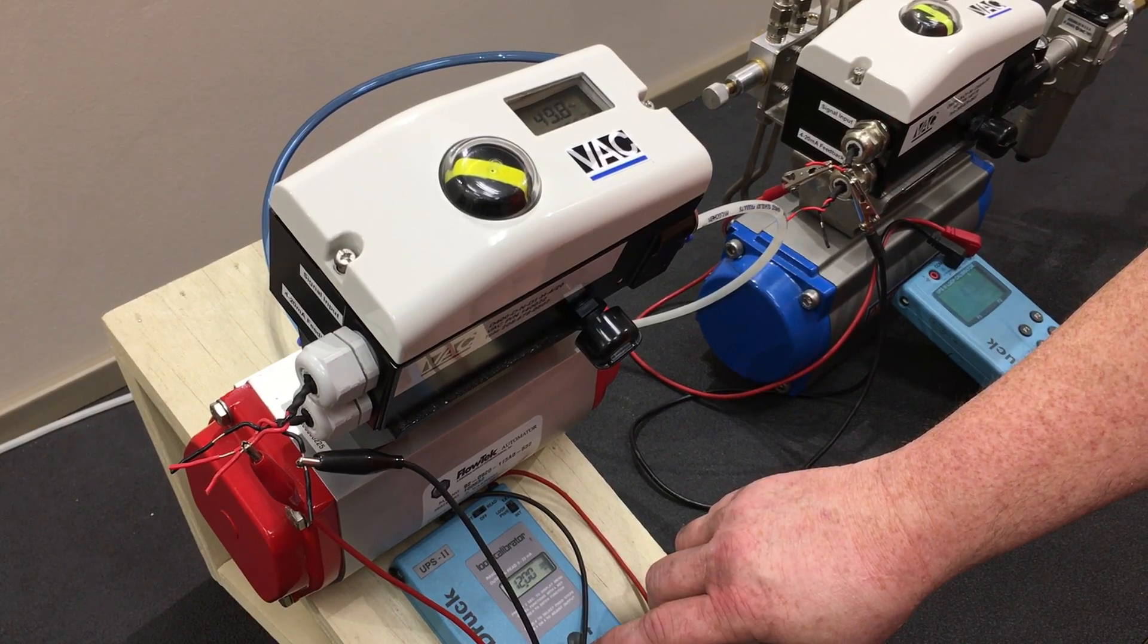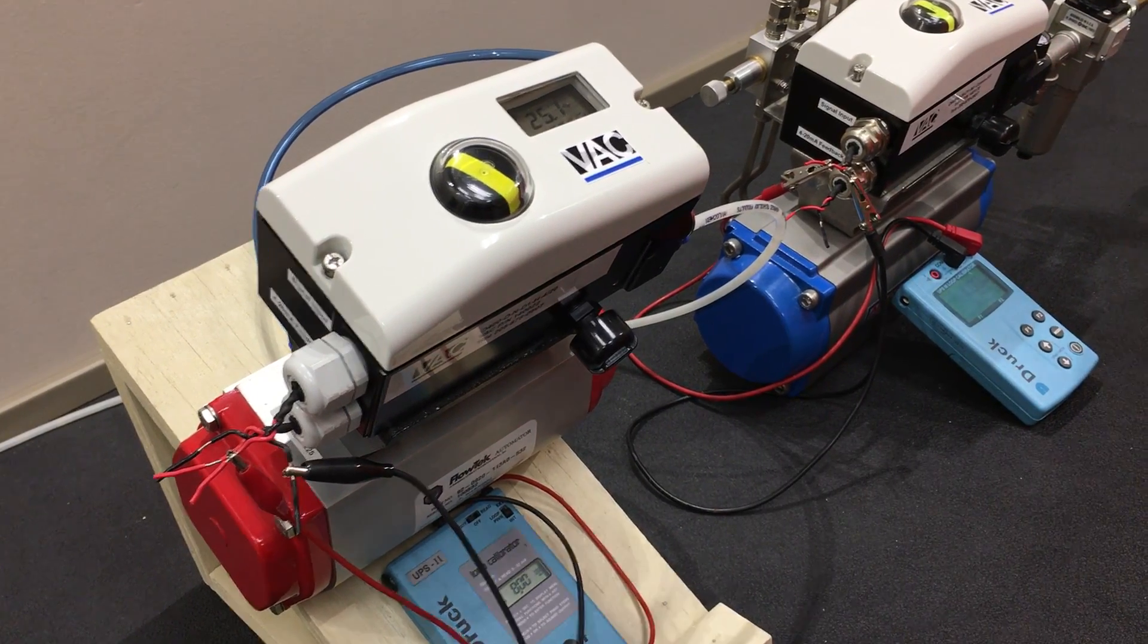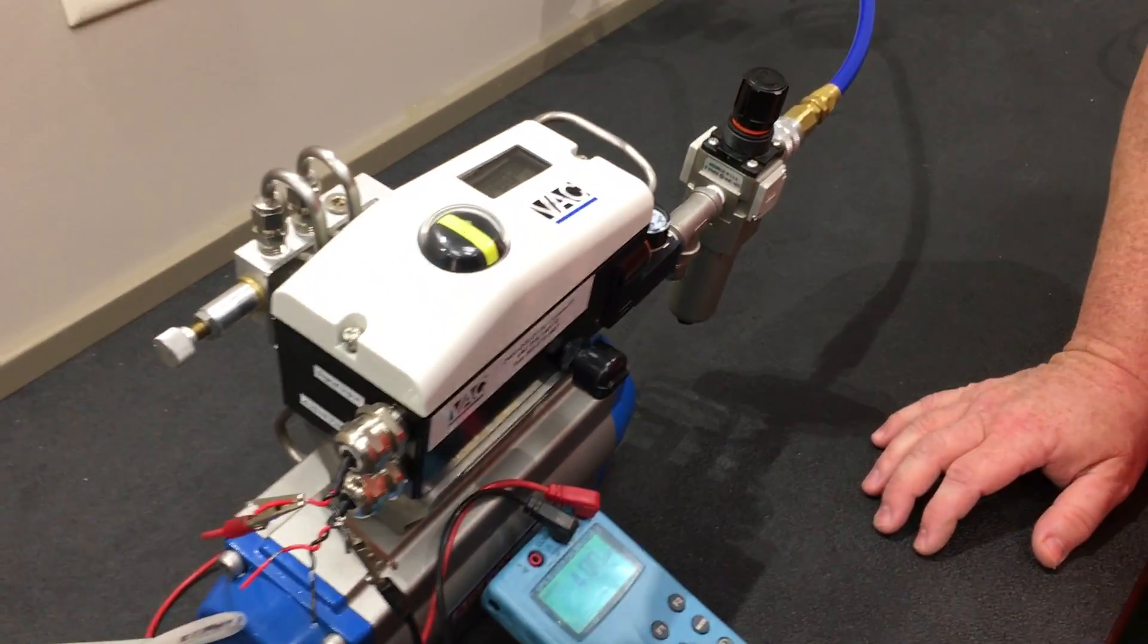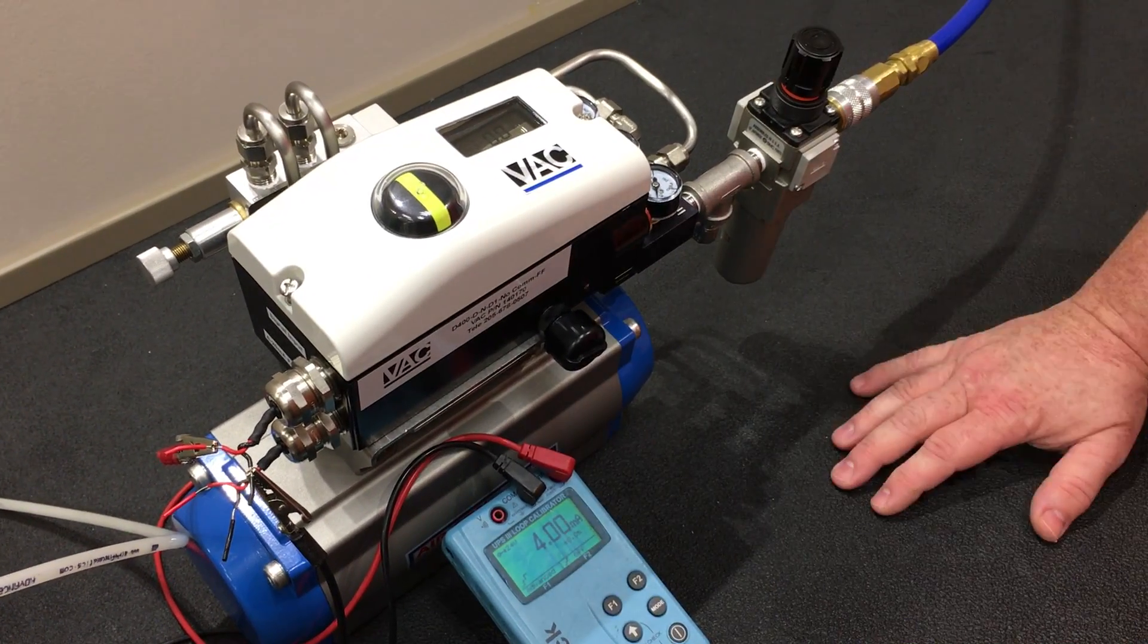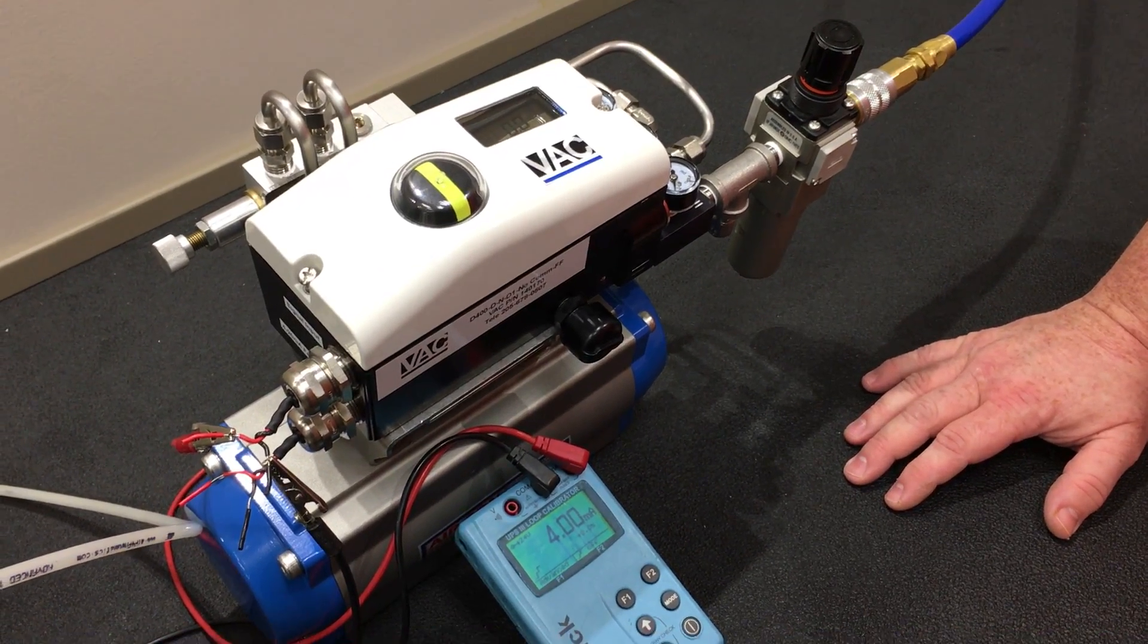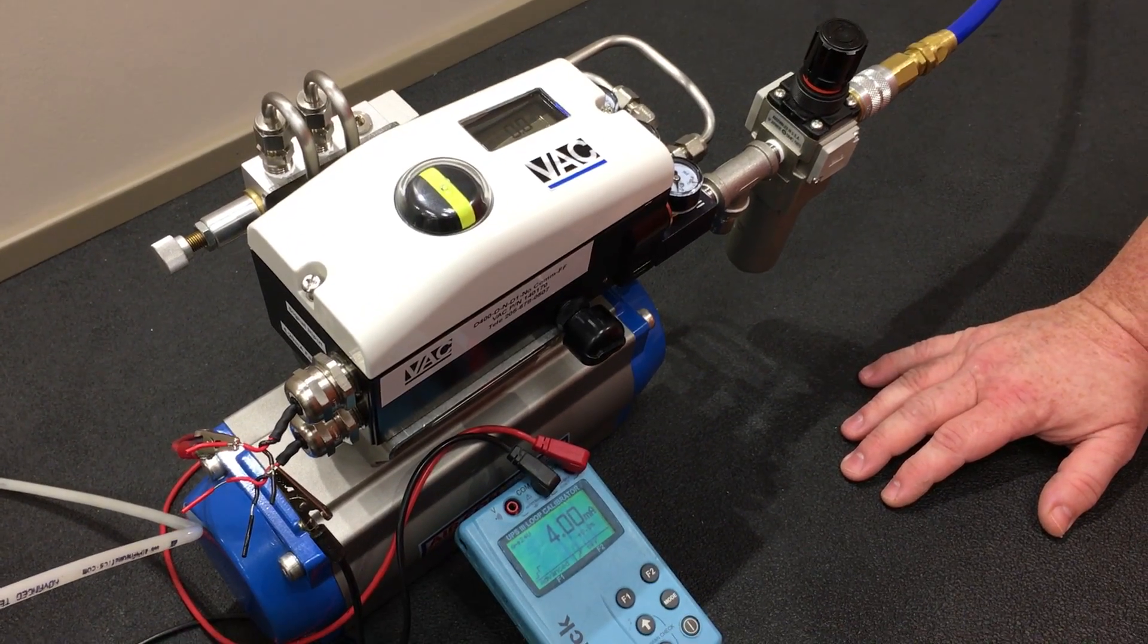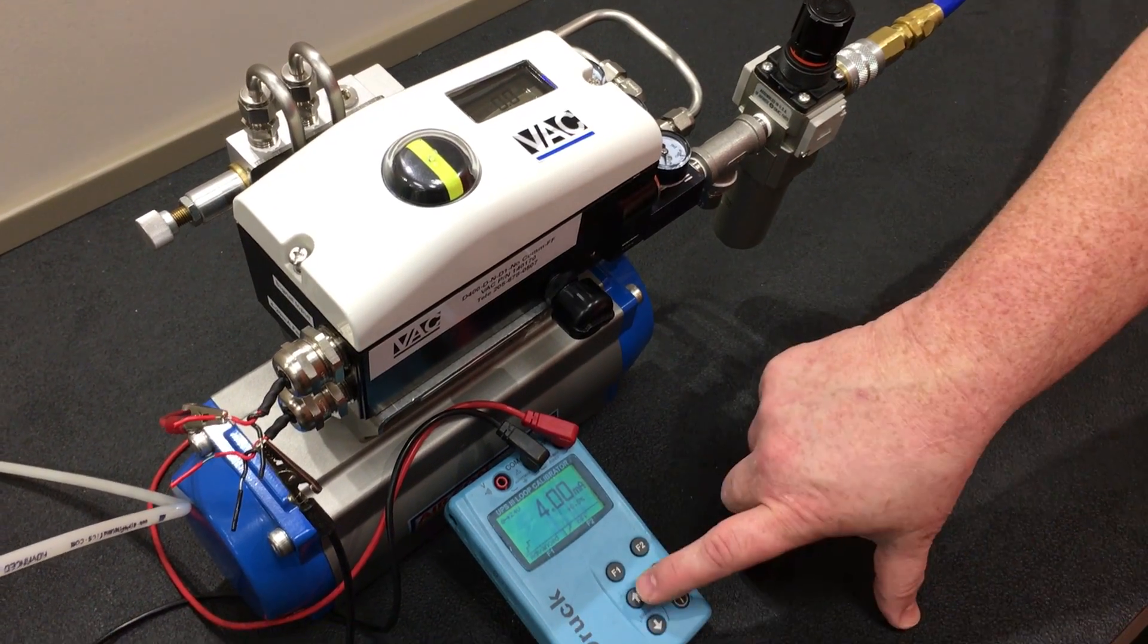Now we're going to look at a fail freeze positioner. With the fail freeze, it will freeze in place on loss of control signal, be that 4 to 20 milliamps.